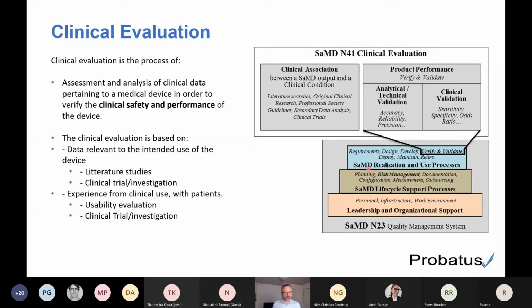Anyways, to establish such a clinical evaluation, it's important to establish a clinical association by looking at the functionalities within the device and stating whether that functionality is relevant and related to a certain clinical area. Second, to conduct an analytical validation, and I'll get to that in a second as well, which is basically the verification activities: testing conducted on the software or the device, checking that we have actually built the device according to specifications, to verify that it's accurate and reliable.